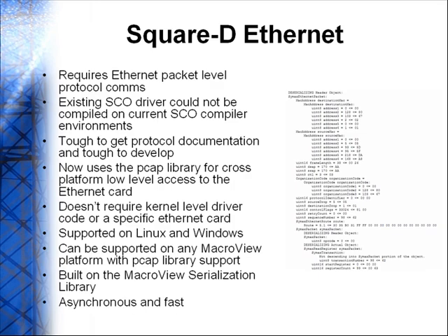It's asynchronous and very fast. Even with an old Square D PLC, you've probably got the fastest responses when you pushed it and set it to the maximum settings. But then, as I mentioned earlier, on a particular Symax 400 Ethernet PLC, it got the PLC into a state, and through the packet sniffing, we came to the conclusion it was the PLC that was the problem, not the driver.